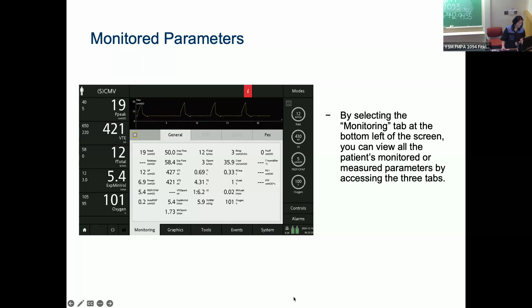Okay. All right. So I would take this opportunity to highlight a feature of this ventilator, which is the flow sensor. The flow sensor on this ventilator, unlike the Avea, is external. And it's not inside the vent, so it's closer to the patient. And it's thought to therefore have more accurate breath-to-breath measurements of volume, flow, et cetera, and pressure.